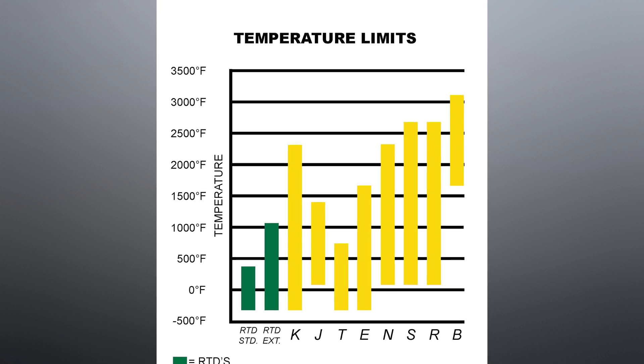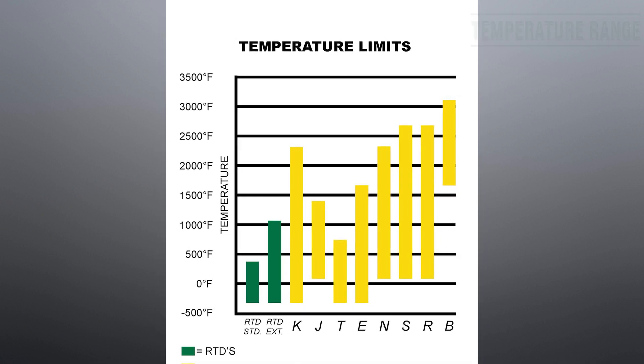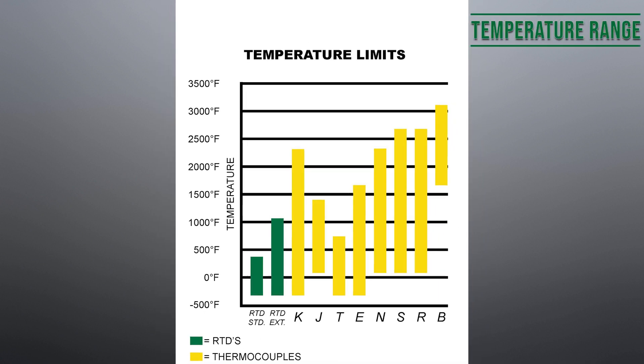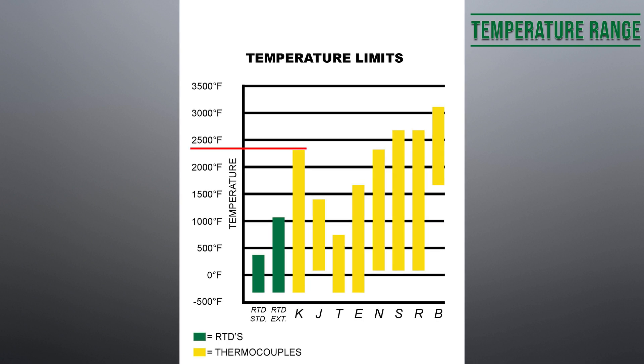One of the most important differences between an RTD and a thermocouple is the temperature range. Base metal thermocouples can reach 2300 degrees Fahrenheit and noble metal thermocouples can reach 3100 degrees Fahrenheit. Compare that to an RTD that has a standard maximum range of 400 degrees Fahrenheit and an extended range of 1100 degrees Fahrenheit.